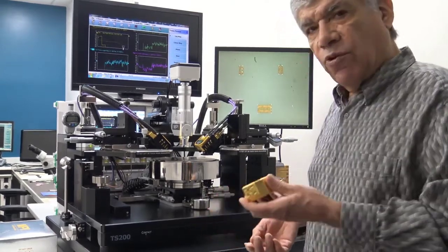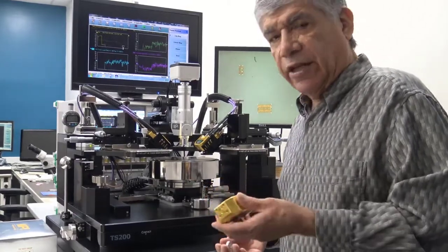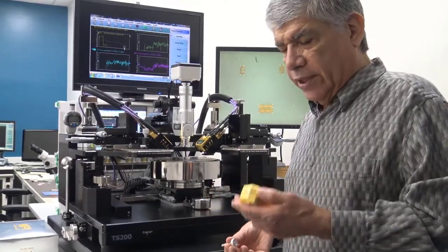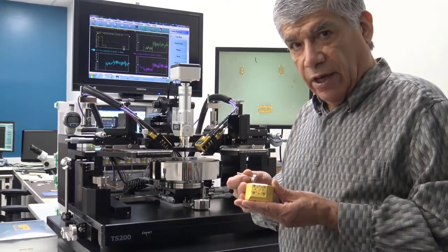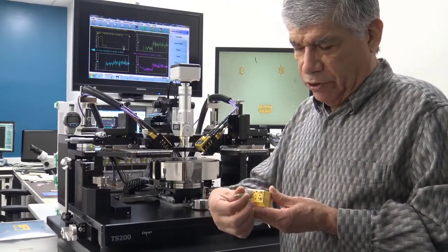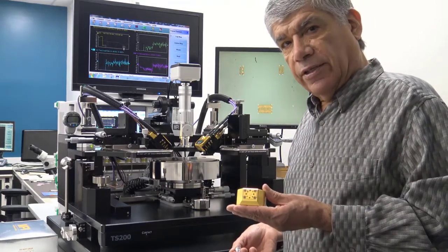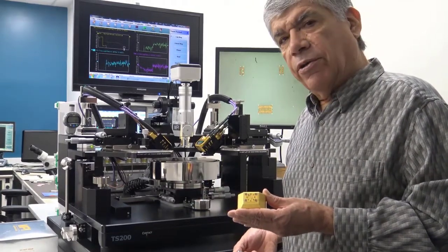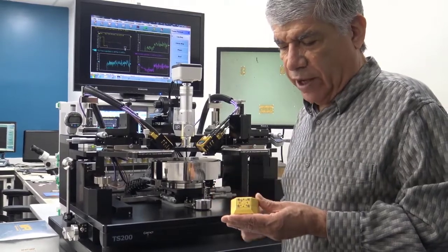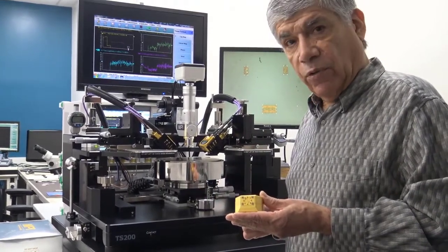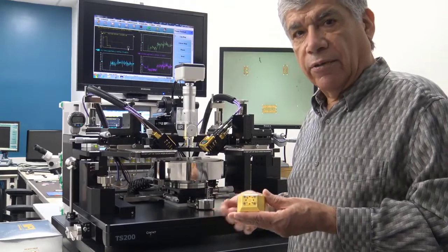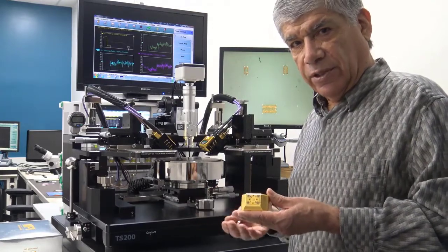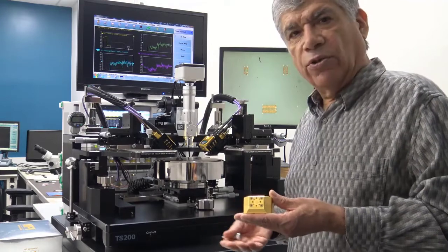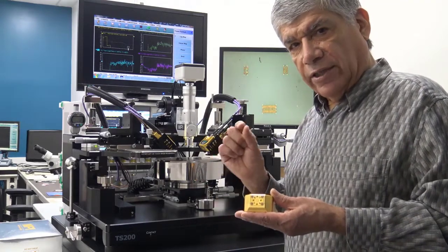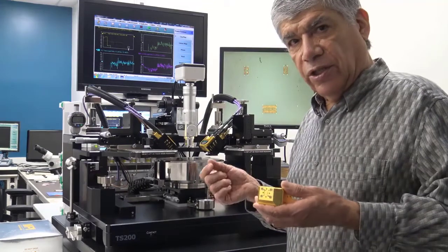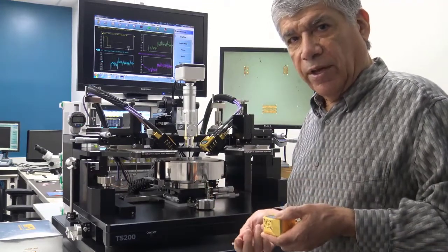Now, in order to get to 220, instead of designing another threaded connector, we decided to create an interface that would directly connect to the probe without using threads. The way that we do that is using a UG387 flange, which is commonly used in waveguide types of measurement systems. The UG387 therefore has the tolerances that allow connection up to 220 gigahertz with good repeatability.